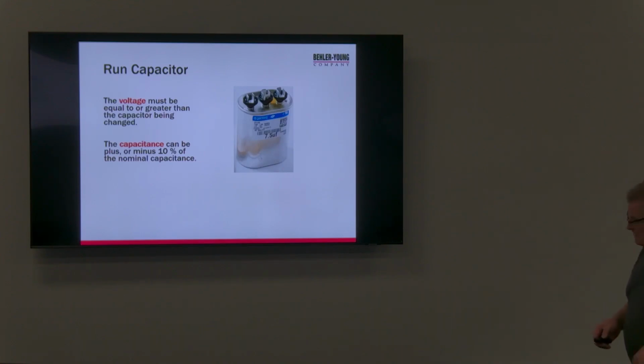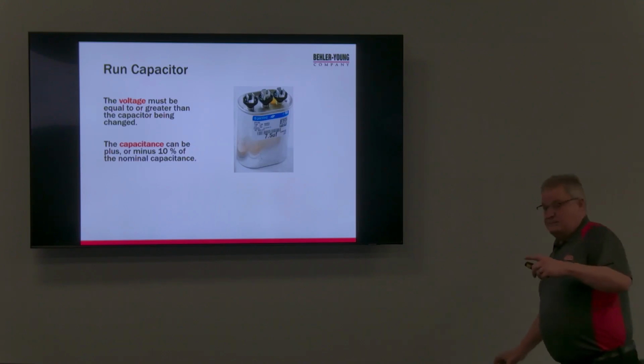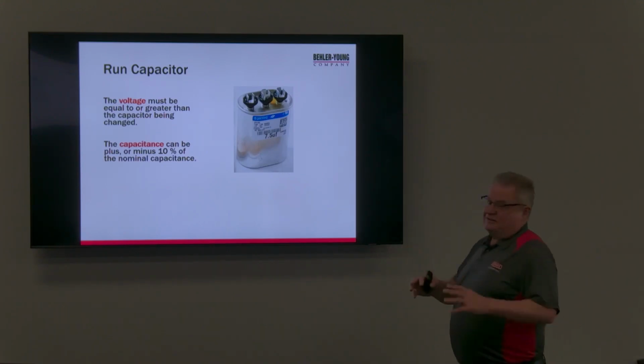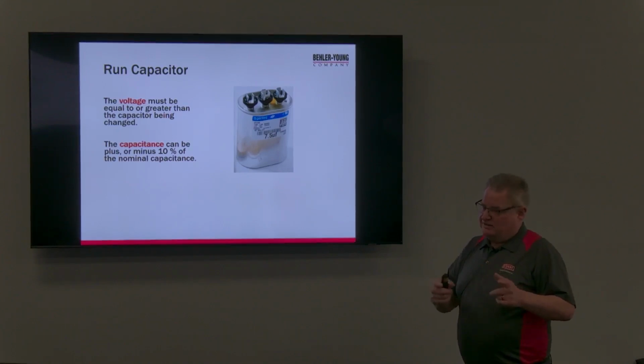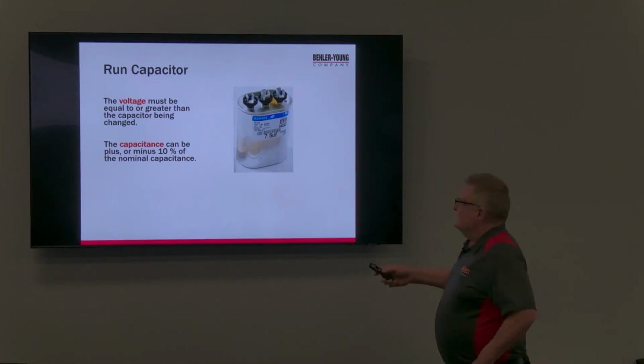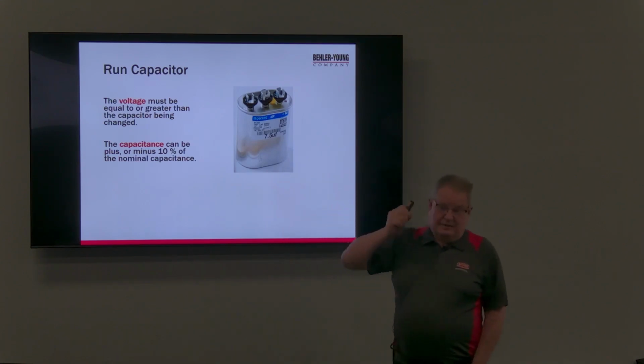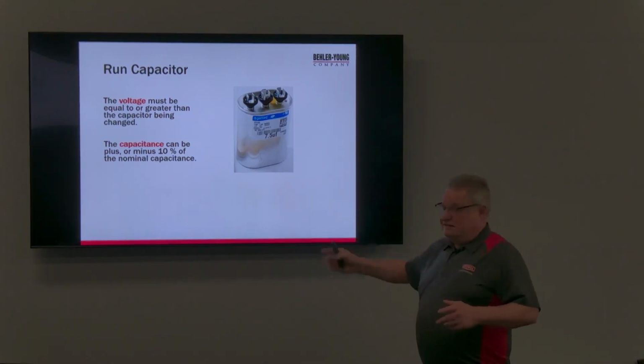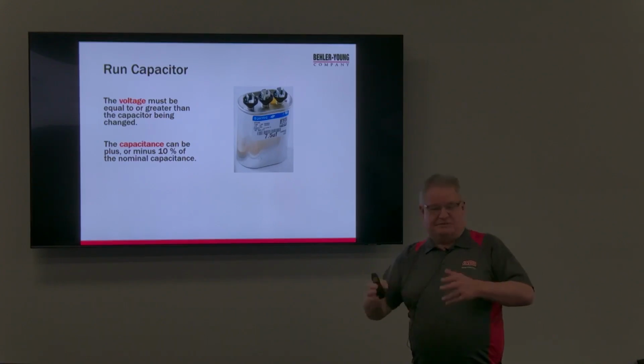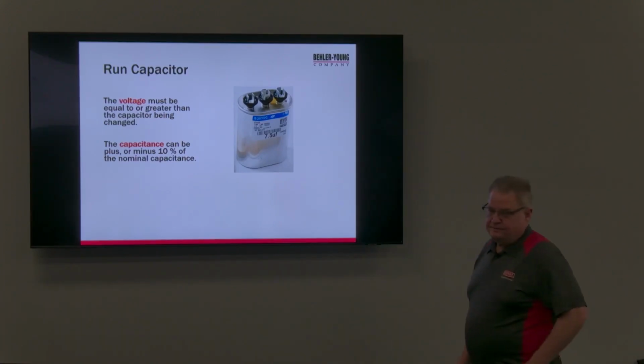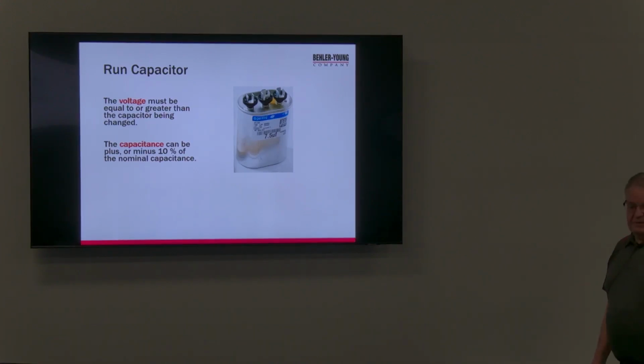Quick question on that. These are labeled plus or minus 6, all of them? Well, that's the difference in the brand, because some of them are tighter than that. That's the way they're rated from the factory. You might get plus or minus 10, that's the cheaper ones. But they'll be plus or minus 6, and some of them are plus or minus 5. That's from the factory, meaning on a run capacitor, it's a 7.5. They're telling you right out of the box, plus or minus 6% or 8% or 10%. That has nothing to do with replacements. But that's a good point, because if it says on there the amount that it's allowed to be off, you have to take that into account.